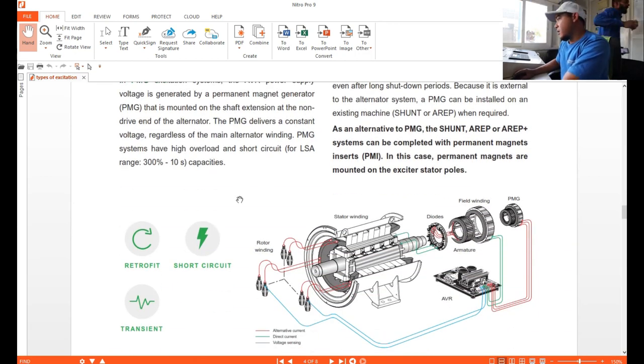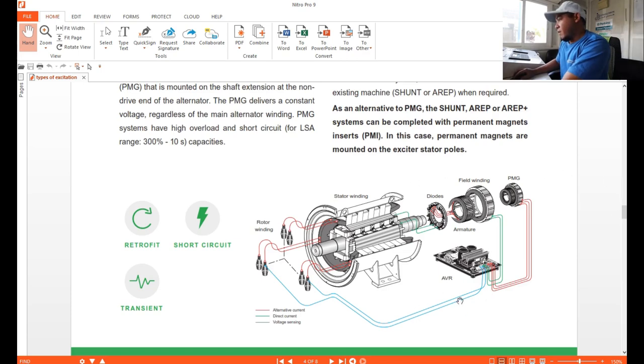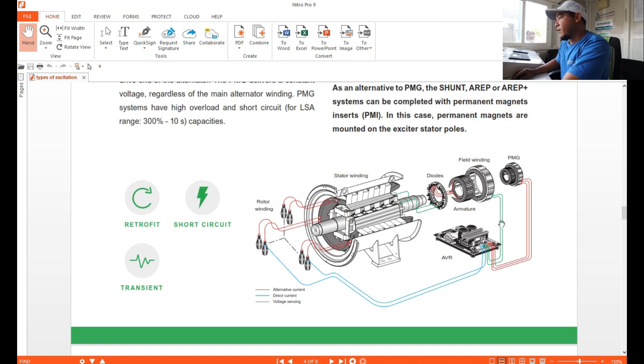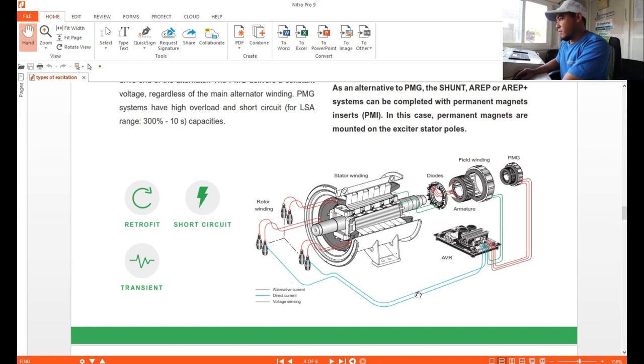Here are the PMG connections on the AVR side: three additional wires are added for the PMG. The red wires are for the PMG wiring connections, the exciter field connections go to the exciter field, and the blue wires are for your voltage sensing point.